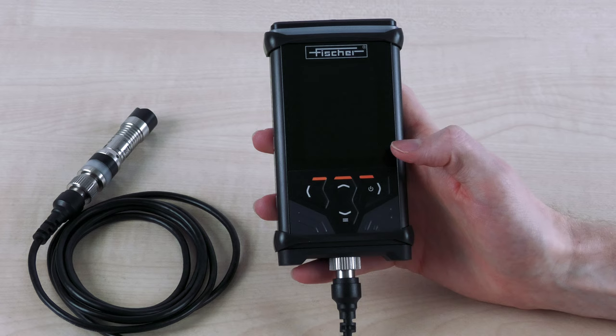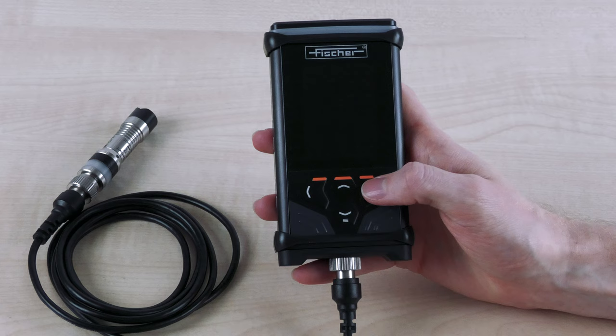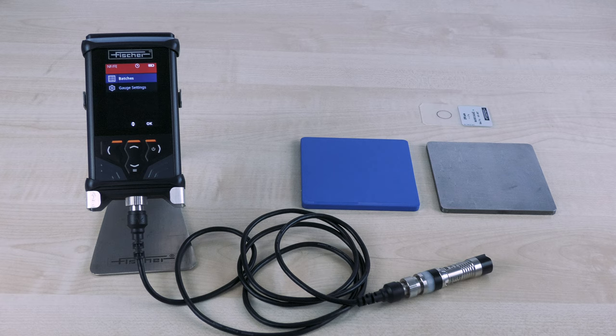After you have inserted the battery and connected the probe to the device, the measuring instrument can be switched on. To do this, press the multifunction button with the on-off symbol printed on it. The graphic display lights up. In order to be able to start measuring, the measuring task, the so-called batch, must first be created. Click on Batches and create a new batch.